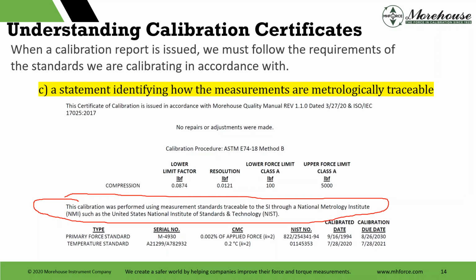They want to see NIST. Our customers, a lot of them want to see NIST. Therefore, you just write that statement on your certificate. No one will complain. When they say, I want a NIST traceable cal, you say, no problem. We're going to issue: this calibration was performed using measurement standards traceable to SI through a national metrology institute, such as the United States National Institute of Standards and Technology, NIST. No one is going to refute this. So traceability is not to NIST, it's to SI through NIST.